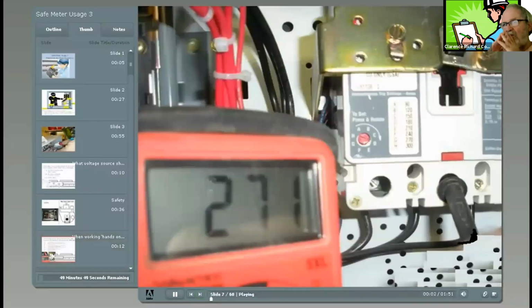Lockout tagout procedure could be renamed lockout tagout verify. If this 480 volt circuit were to be worked with hands-on, the breaker disconnect must be tripped, of course, before doing so. The verify step in this instance does not mean the circuit is safe to do hands-on work, just because the breaker disconnect is locked out, and the push of the start button did not pull in the contactor.